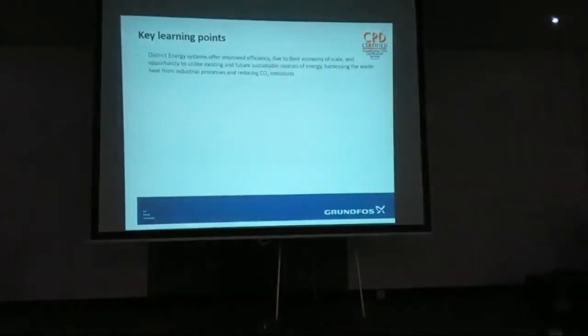Right, key learning points. We've only got a few slides left. District energy systems offer improved efficiency. A bigger centre serving a wider area is better than individual boilers all over the place. With a probable demand scenario, if you've got 200 HIU units or 500 HIU units, there's not a huge difference in the boiler plant needed to feed that. If you had individual boilers all over the place, it would be a colossal amount of energy. So it's better to go for a district one wherever possible.